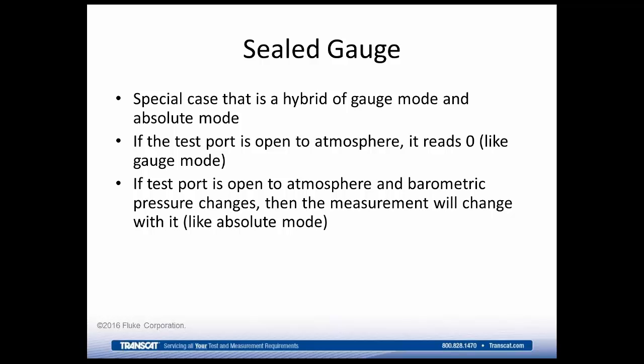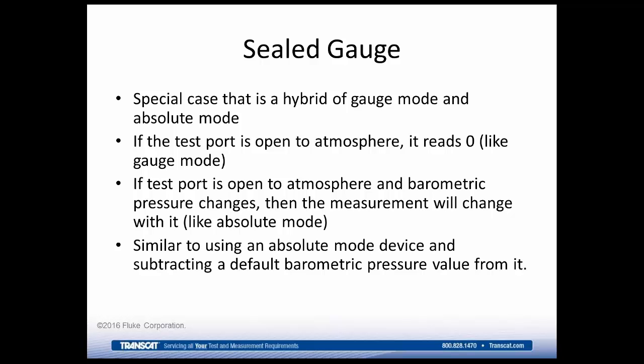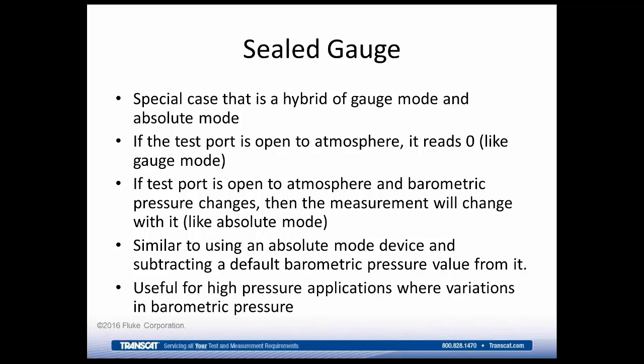So basically it's a gauge-like reading, but the backside of the measuring device, of the sensor, is sealed off and is not actually open to atmosphere. So it doesn't stay at 0 with atmosphere changes. So it's similar to using an absolute mode device and subtracting a default barometric pressure value from it. And this is useful for high pressure applications where the variations in barometric pressure don't affect your overall measurement.